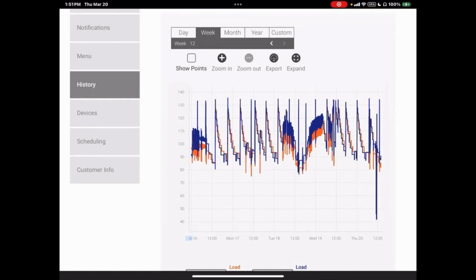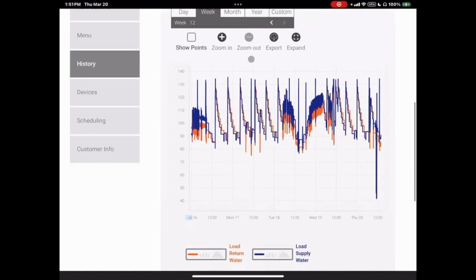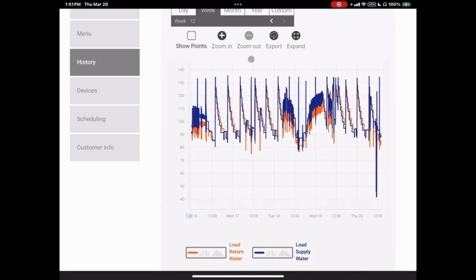Well, I know one of the questions that came in: what do you do with a very large domestic hot water load? Let's say we've got a very large master bathroom shower, and the load is actually larger than the space heating load. If you're going to address a load like that, you'd have to have the capacity to do it first of all. So either dual fuel with the boiler running, or the electric unit with the electric elements running, or possibly even multiple units, depending on what that demand was.